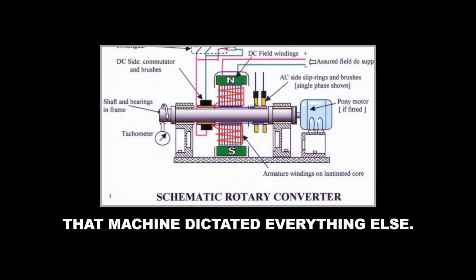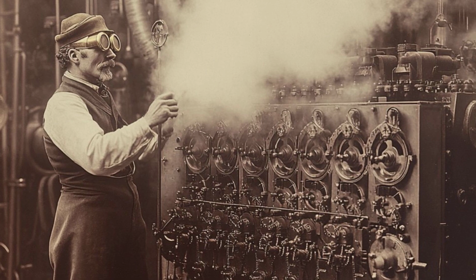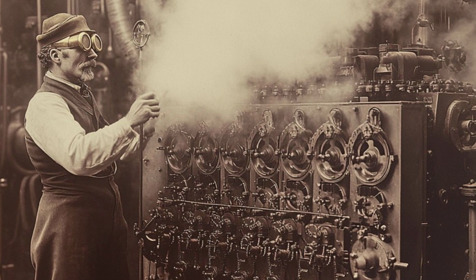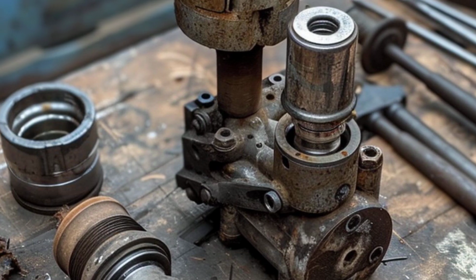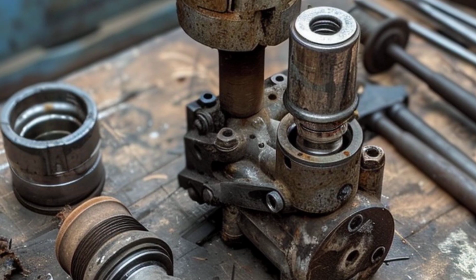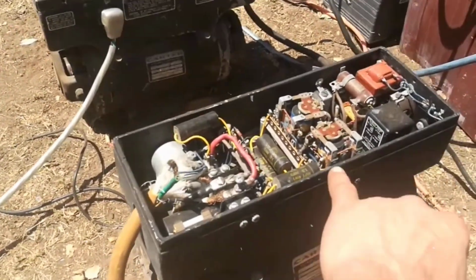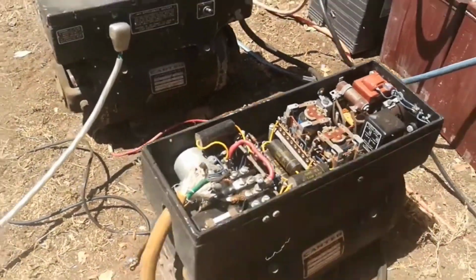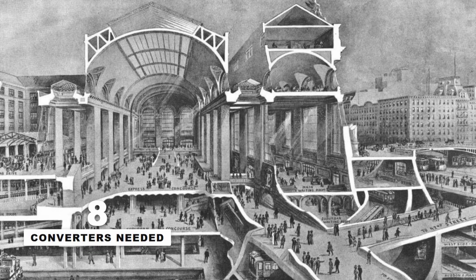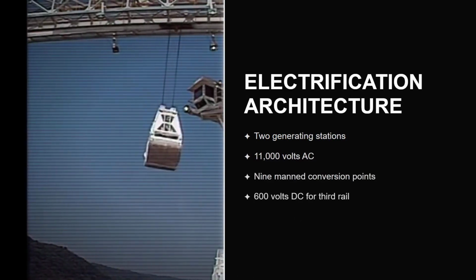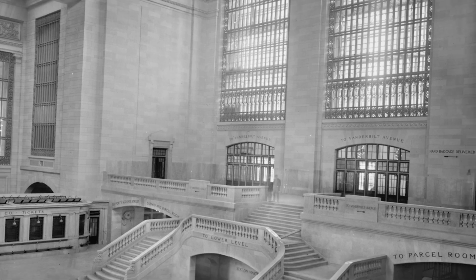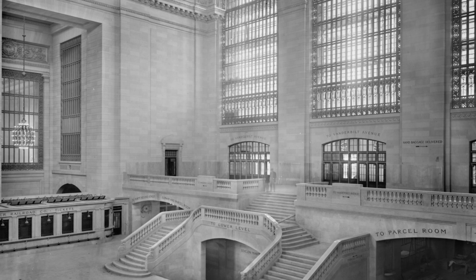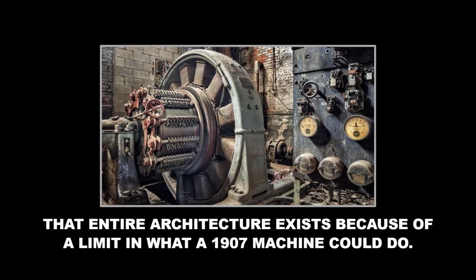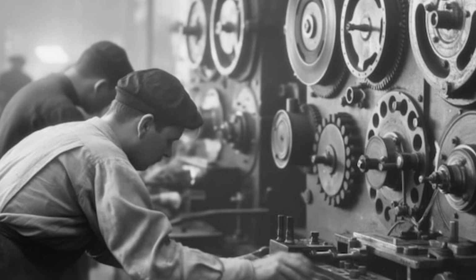That machine dictated everything else. It had to be housed. It had to be manned. Staff started and stopped individual converters around the rush hours by hand, because running one when it was not needed simply wore it out. Behind it, you needed a battery room, because a machine that spins can stop. And you needed 9 of them strung along the line, because 600 volts of direct current will not travel far down a third rail. Two generating stations, 11,000 volts of alternating current, and 9 manned conversion points.